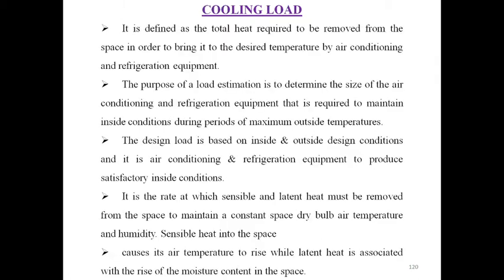Cooling load is the total heat required to be removed from the space in order to bring it to the desired temperature by air conditioning and refrigeration equipment. Load estimation determines the size of air conditioning and refrigeration equipment required to maintain inside conditions during periods of maximum outside temperatures. The design load is based on inside and outside design conditions.